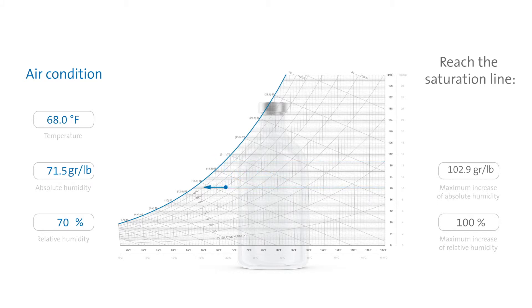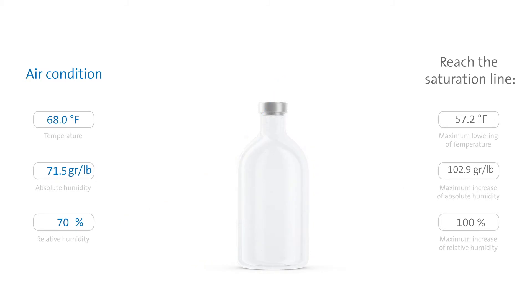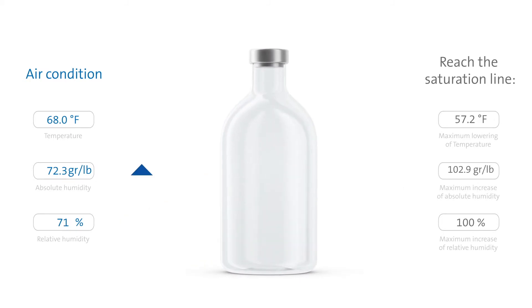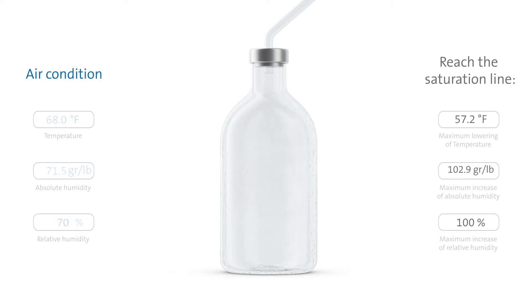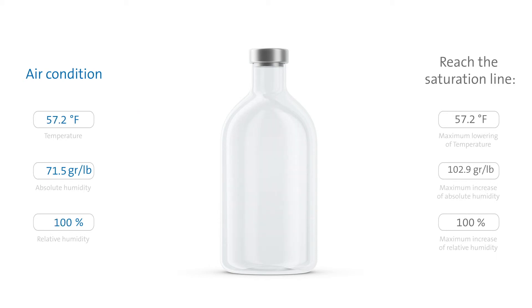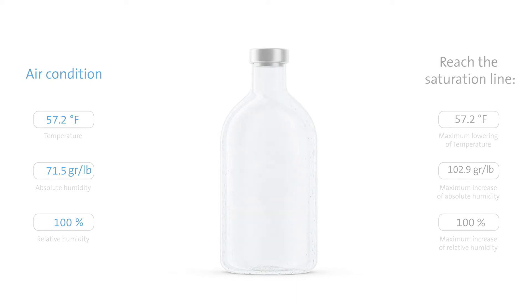We know that the air in this state will also reach the dew point line if it cools down by at least 10.8 degrees Fahrenheit. If we now add steam to the flask and increase humidity, mist would then form followed by condensation as soon as we reach 102.9 grams of water per pound of air. Or, alternatively, if we decrease the temperature by 10.8 degrees Fahrenheit, the air would also reach the saturation line — first mist, then condensate would form.